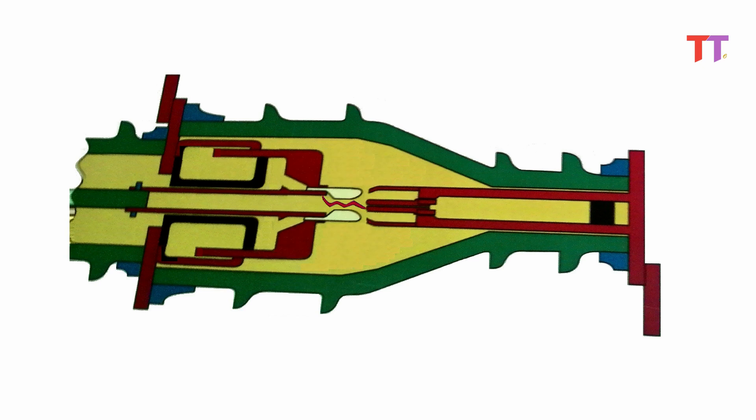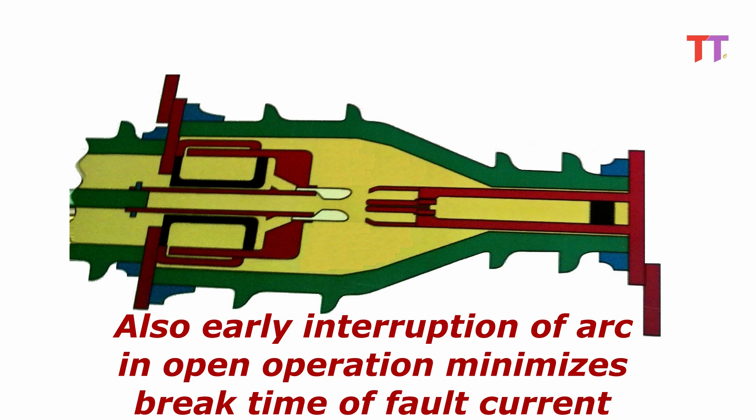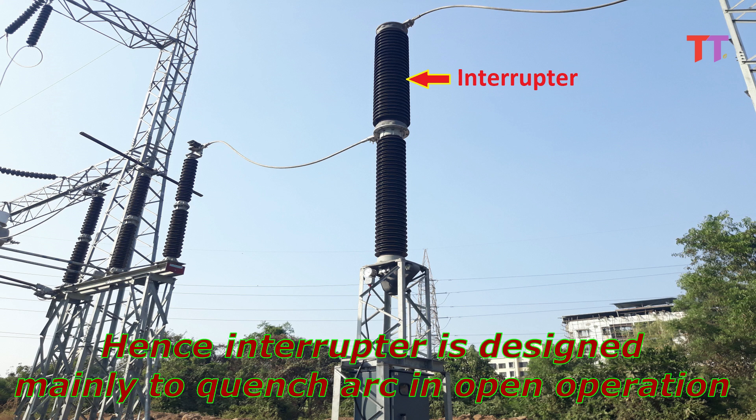But in open operation, contacts move away from each other. Arc is formed and it gets elongated as contacts move away from each other. This phenomenon persists longer. Also early interruption of arc in open operation minimizes break time of fault current. Hence interrupter is designed mainly to quench arc in open operation.